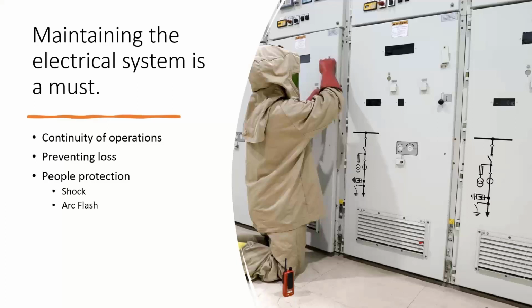the upstream protective device. There's a breaker somewhere or a fuse or something, hopefully upstream, that's going to say, hey, there's a problem down here. I need to clear this fault. I need to open up. And that time that it takes to do that is based on some protective relay settings that you might have and how long it actually takes that breaker to operate.